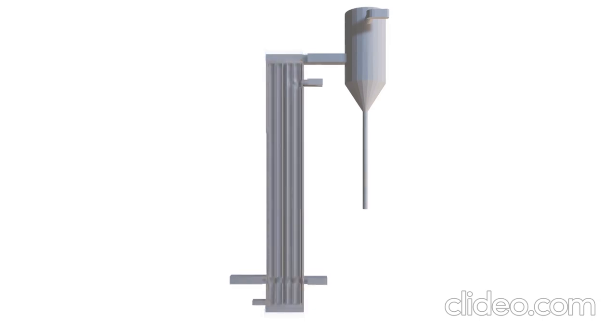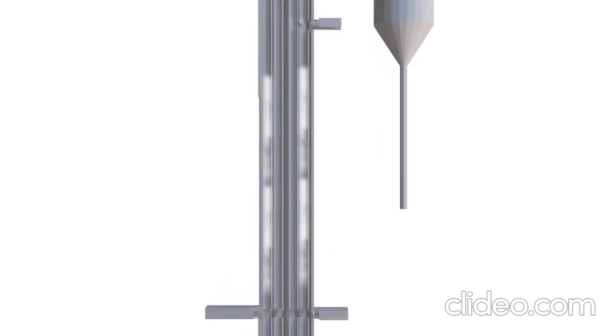Its theory is that vapor travelling faster than the liquid flows in the core of the tube causing the liquid to rise up the tube in a film. When it occurs, the liquid film is highly turbulent and high heat transfer rates are realized.